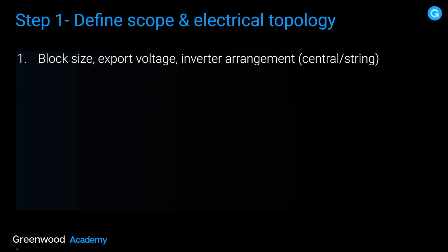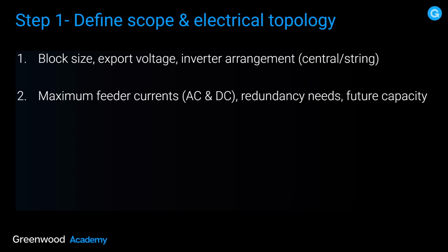Step 1, define the scope and the electrical topology. So first things first, look at the block size, export voltage, and the inverter arrangements. Is it a central or string? In most cases with a solar farm, you're looking at a central inverter, but not always. 2, look at the maximum feeder currents, both AC and DC. Take into consideration the redundancy needs and future capacity.